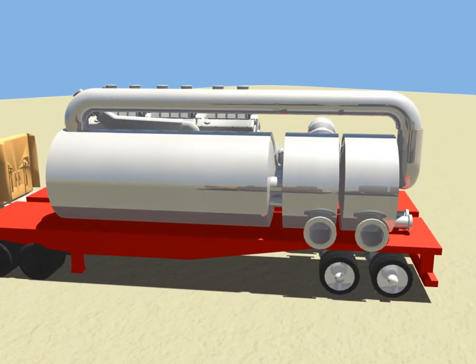The three main components of the MVR truck are the evaporator tank, heat exchanger, and the preheater economizer. The evaporator tank utilizes a natural gas heat source. The clarified brine stream enters the preheater, which uses heat from the MVR distillate. The preheated brine stream enters the evaporator tank, where volatile components and water are vaporized out of the waste liquor, which consists of salts and other non-volatile waste contaminants. The vaporized stream is sent to the compressor.